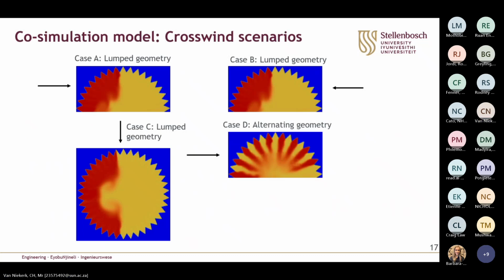So to do so, we considered the four following crosswind simulation scenarios. Cases A, B, and C correspond to the lumped geometry, where case A has the crosswind blowing from the left to right into the pre-cooler, case B with the crosswind from the right to left blowing into the intercooler, and C with the crosswind blowing from the top down into both the pre-cooler and intercooler. However, in this case, the effect is not symmetrical, and we actually had to extend the model to include a full tower in the domain. And then finally, case D, which is the alternating geometry with just the crosswind blowing from the left to the right. And in this case, the flow is assumed to be symmetrical, so we only consider this one crosswind direction.